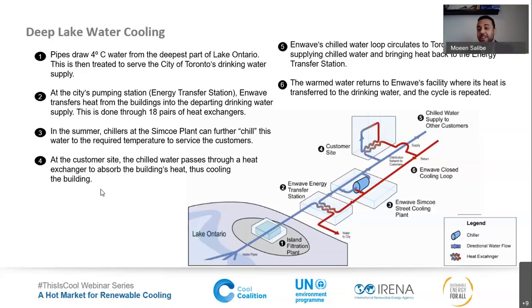The water is fine and still cold. On the other side of the heat exchangers, or the ETS, is the Enwave system, which is a completely closed loop system. We exchange the water with high efficiency heat exchangers and push this water to the customers. At point three, this is our cooling plant, which includes electric driven chillers, used during peak times and emergencies or when lake water is not available, and we push the water to the customers.